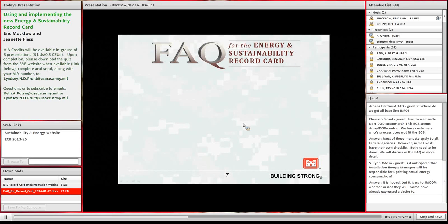Where Jeanette is up there in the upper northwest, there's a lot of hydro. The DOE does publish conversion factors for different regions. They will tell you what you need to multiply your electricity from the grid by to figure out what proportion of it is fossil and the remainder then is non-fossil. That can be done, and so if you don't meet the energy target with just putting everything in fossil, which is the worst case scenario, you can multiply by that factor and put the non-fossil fuel down on the non-fossil blank, and that might help you out.